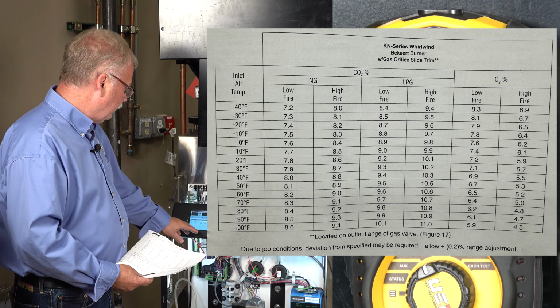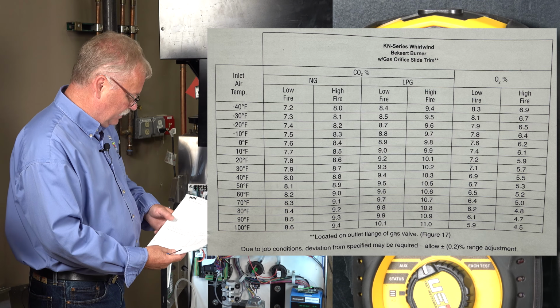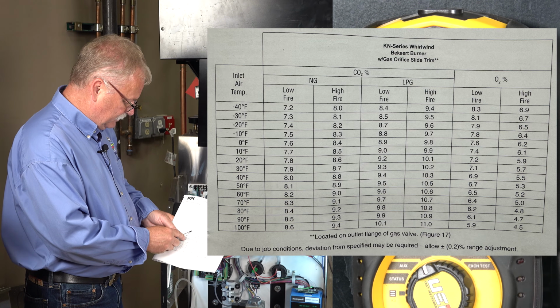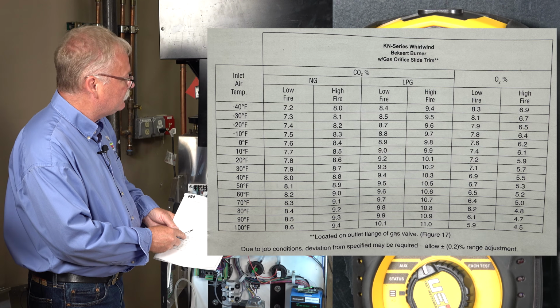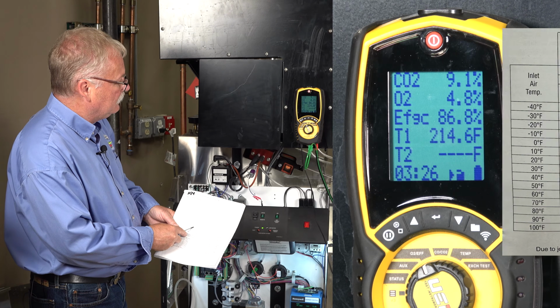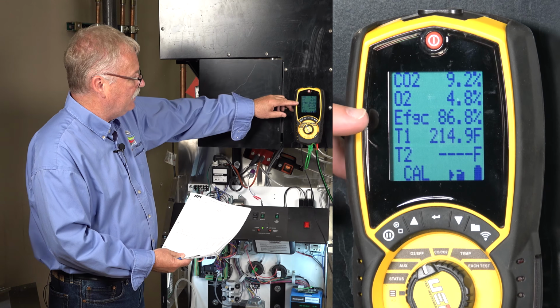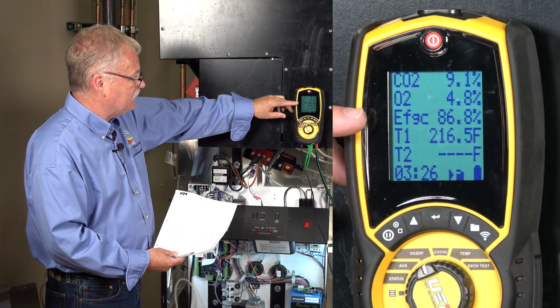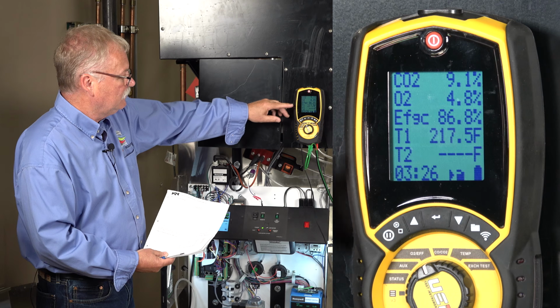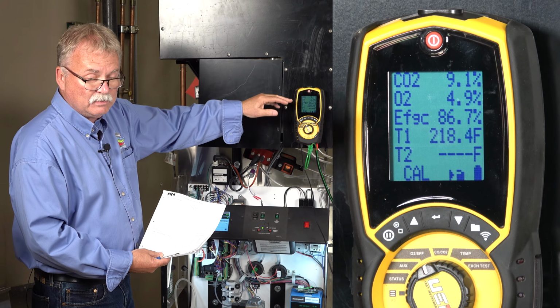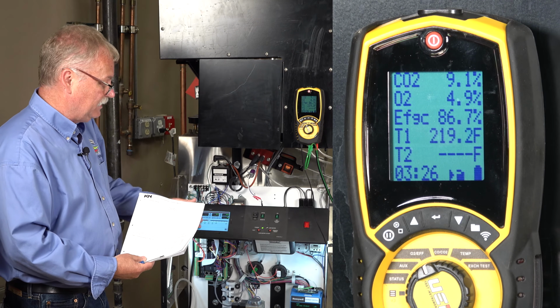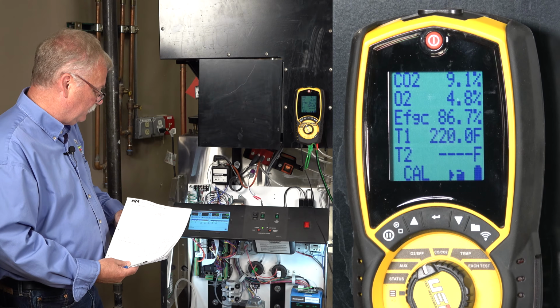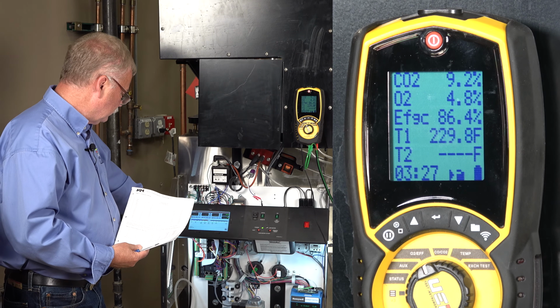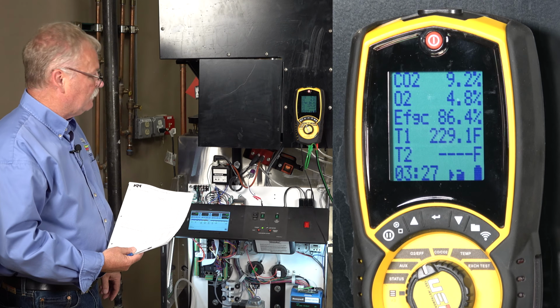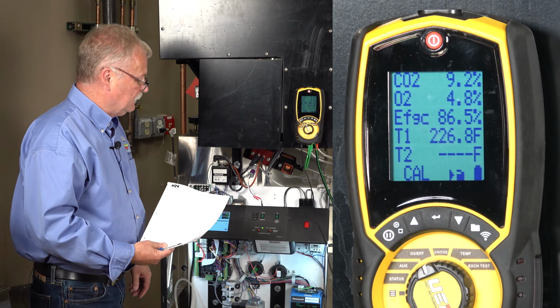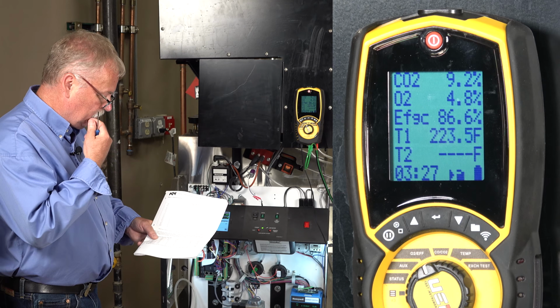So now our high efficiency seems pretty well close to being in range. High efficiency should be 9.2. I'm sitting at 9.1. And my efficiency when I first started, which was almost 97%, is down to 86. The longer I run this, probably the more it will drop down. But let's get to actually playing with the burner itself now in the gas valve. I'm going to force it all the way down to low so the set point doesn't take over. And we're going to look at how to adjust it.